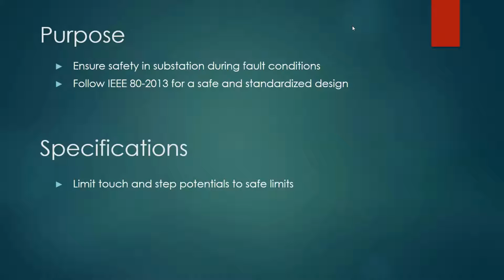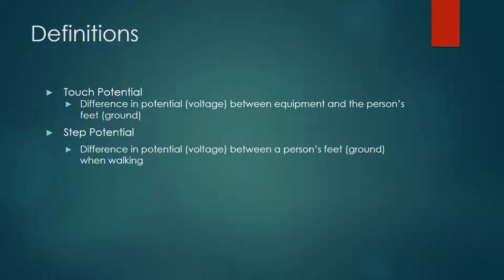Next, we're going to talk about the grounding grid. The purpose of a grounding grid is to ensure safety in substations during fault conditions. Our grounding grid was designed to IEEE standard 80-2013. For specifications, we want to limit the touch and step potential below safe limits. So we're just going to hit a few quick definitions.